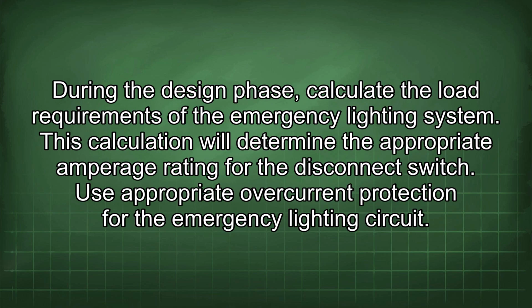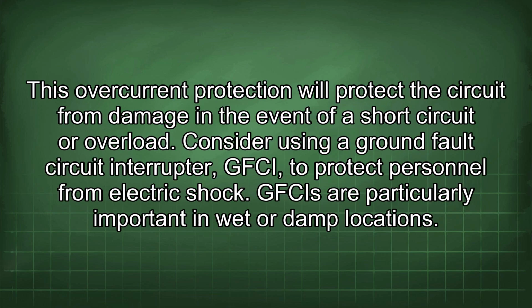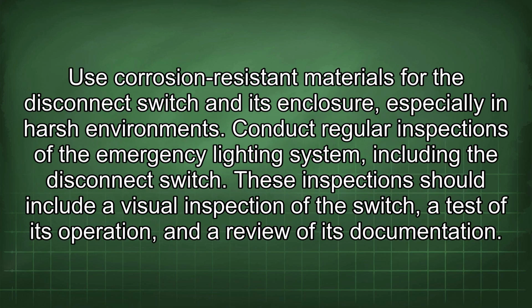During the design phase, calculate the load requirements of the emergency lighting system. This calculation will determine the appropriate amperage rating for the disconnect switch. Use appropriate overcurrent protection for the emergency lighting circuit. This overcurrent protection will protect the circuit from damage in the event of a short circuit or overload. Consider using a ground fault circuit interrupter, GFCI, to protect personnel from electric shock. GFCIs are particularly important in wet or damp locations. Use corrosion-resistant materials for the disconnect switch and its enclosure, especially in harsh environments.